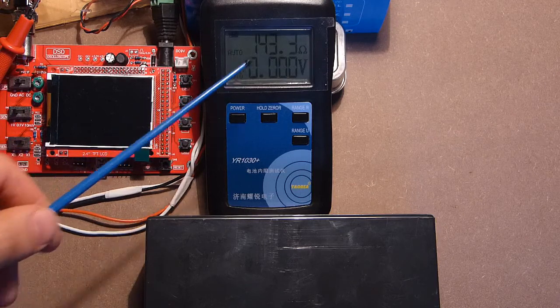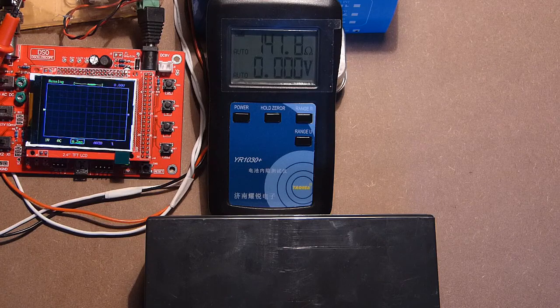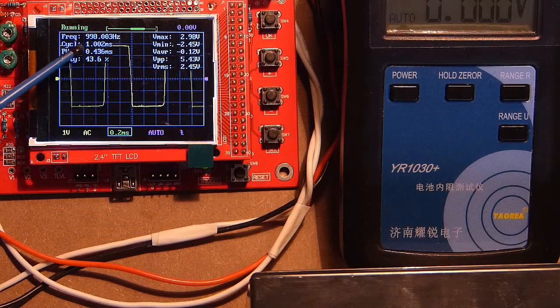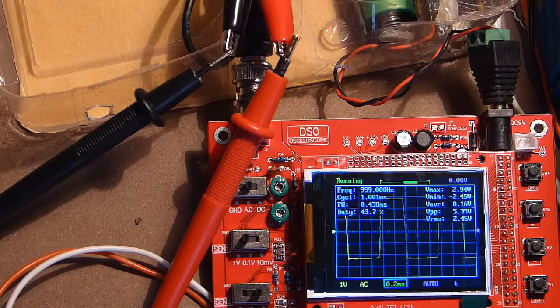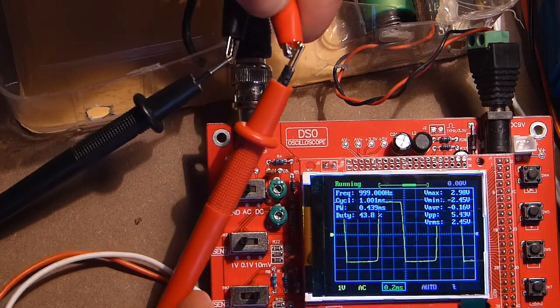Finally, let's check the frequency of this device and its waveform: 997, 998, sometimes 999. So we can say that the frequency is really 1 kHz and the waveform is square. Also, please pay attention to the fact that the oscilloscope probes are connected directly to the impedance meter probes. Otherwise, we will have a distorted signal, like this.